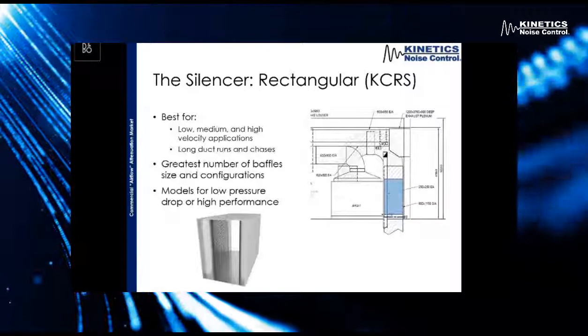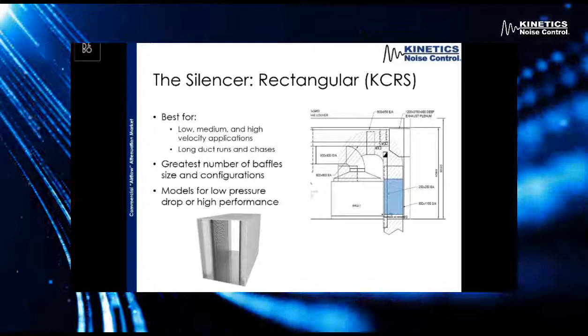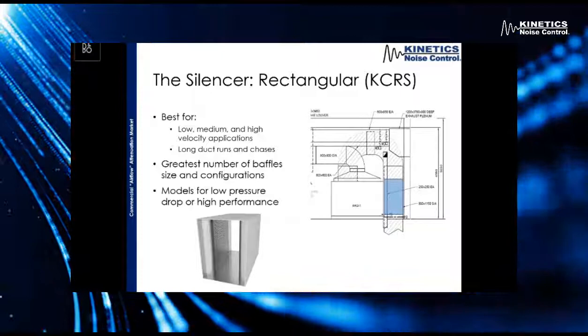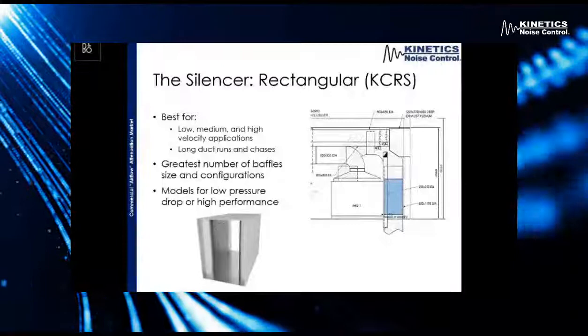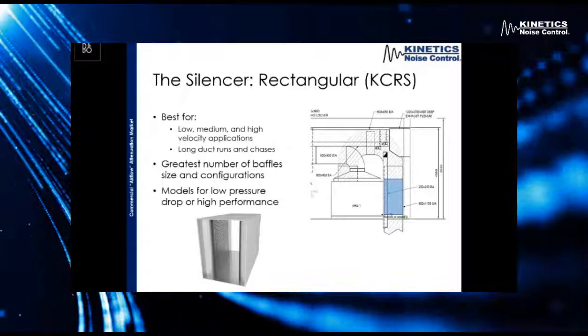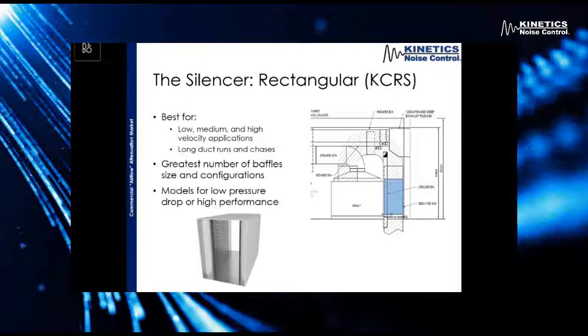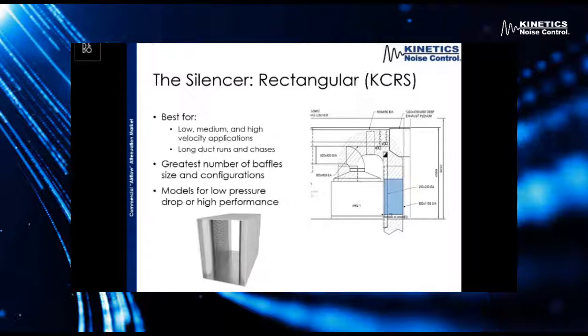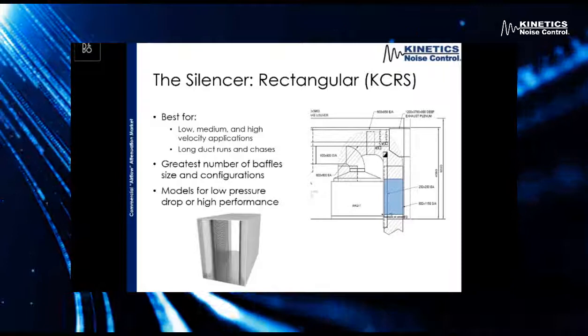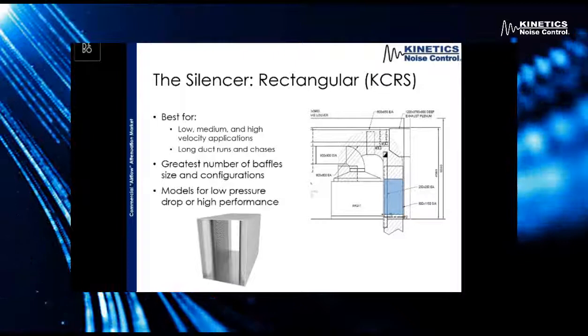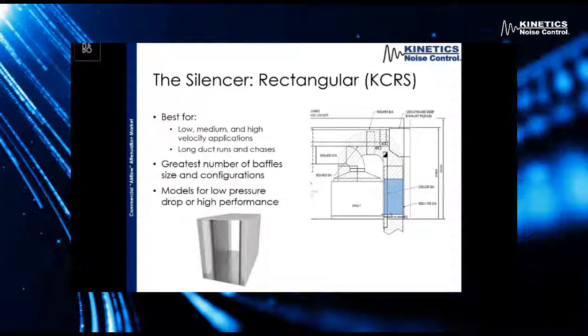We have three different standard types of silencers. The first is rectangular — this one is by far the most versatile. When it comes to the baffles inside a rectangular silencer, we have the greatest versatility in the size and configurations of baffles we can use. The configuration becomes important because we can start tuning our silencers to be good for low, mid, or high frequency noise. Rectangular silencers can also be made well suited for low, medium, and high velocity applications, giving us a good balance of acoustic performance — insertion loss and pressure drop. These silencers are really good for long duct runs or chases, places where you'll actually start seeing those ideal system effect conditions.